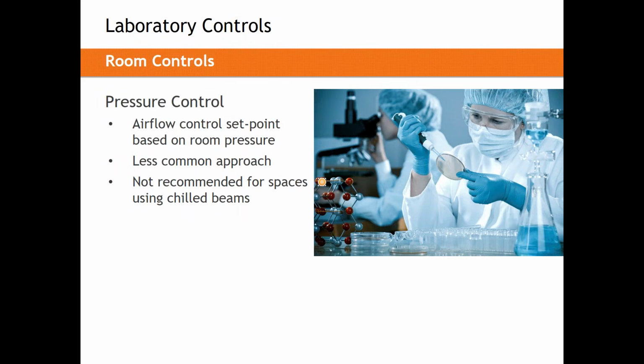In a high traffic space like an operating room, when the doors are constantly being opened and closed, pressure control starts to fall apart. It can either be driven wild by the doors, or more appropriately, doors opening and closing would freeze this system, making pressure control really turn into volumetric offset control. In a laboratory environment, specifically with fume hoods, when you're drastically changing the exhaust airflow rate, you're doing it by a large amount and you're doing it often with these fume hoods, pressure control can be driven nuts, meaning it's trying to make these rapid changes to achieve a very accurate small pressure in the space. The fume hoods will just drive it wild all the time.